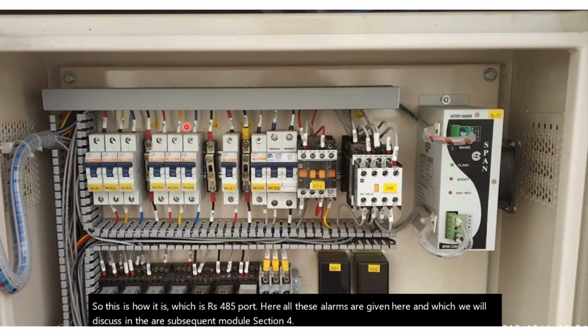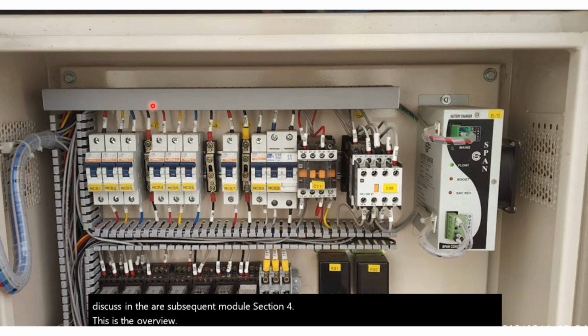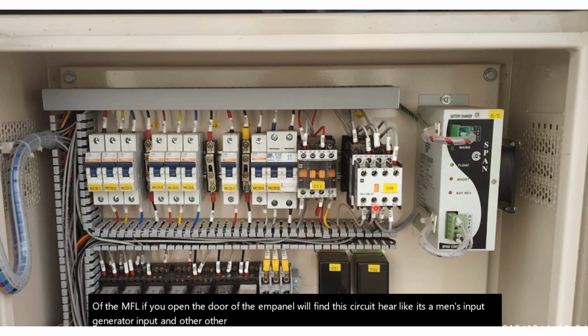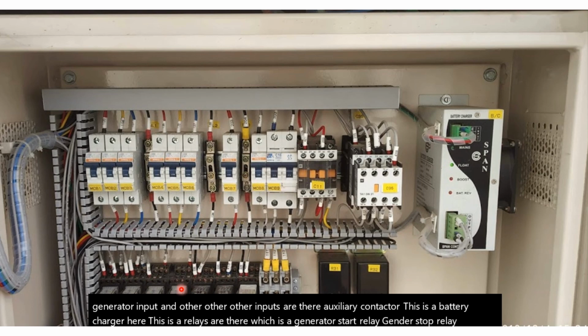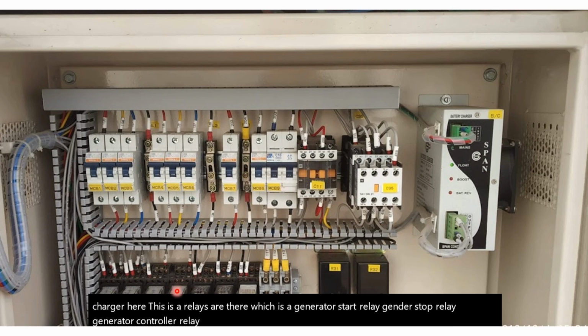This is the overview of the AMF panel. If we open the door of the AMF panel, we will find this circuit here: a mains input, generator input, and other inputs. Auxiliary contactor, this is a battery charger. Here are the relays: generator start relay, generator stop relay, generator controller relay, mains generator contactor relay, mains contactor relay, common fault relay. All these relays have been given, and their function and wiring we will be studying in the next section.